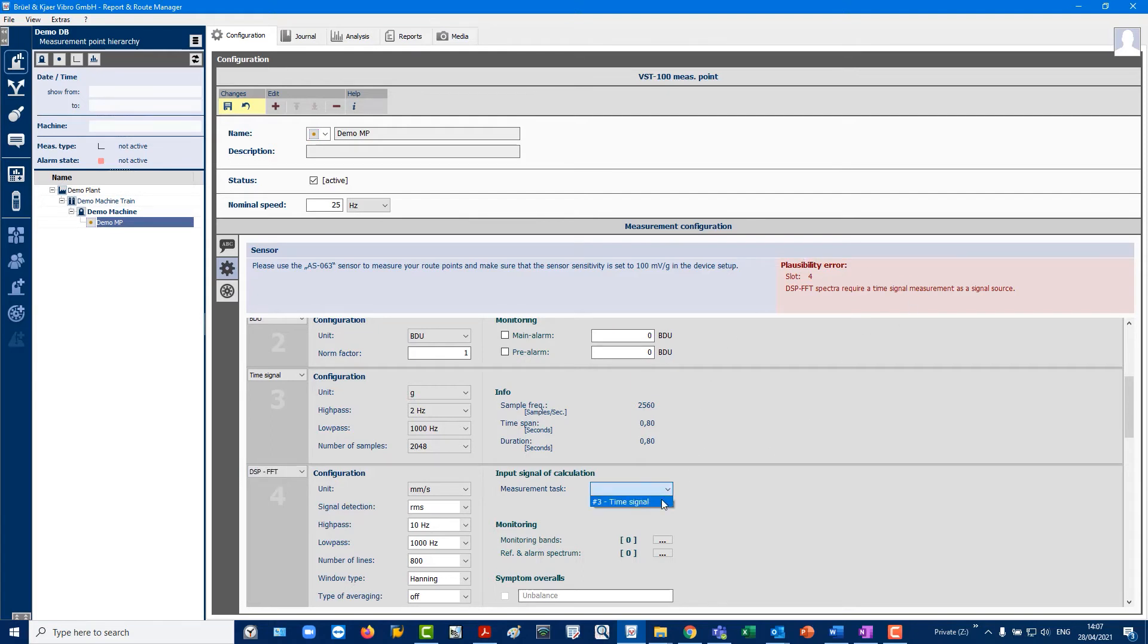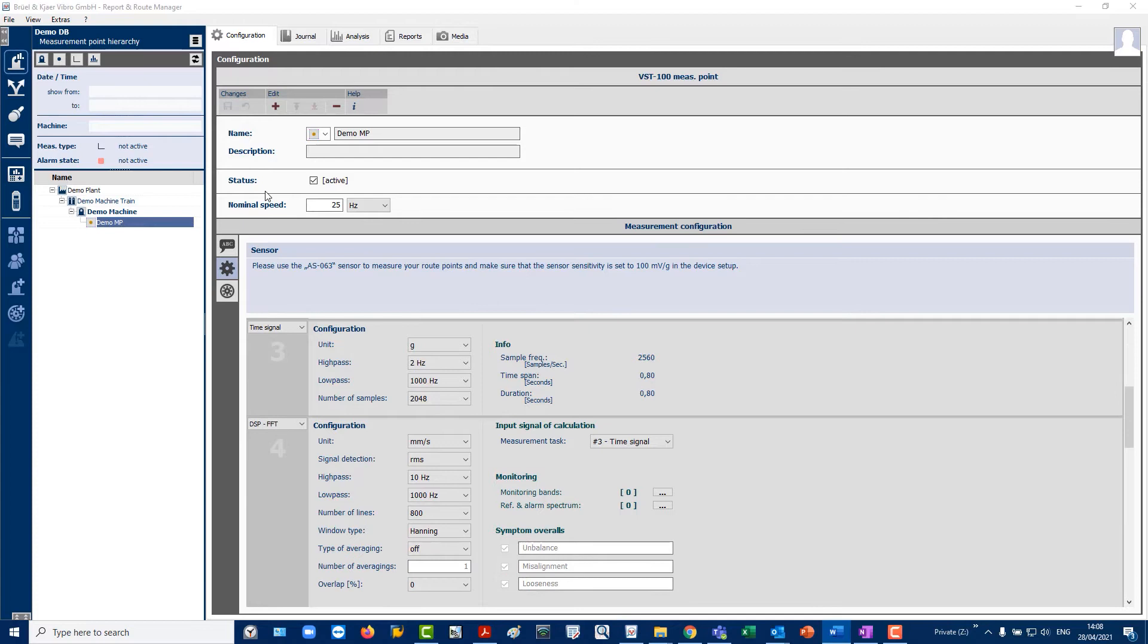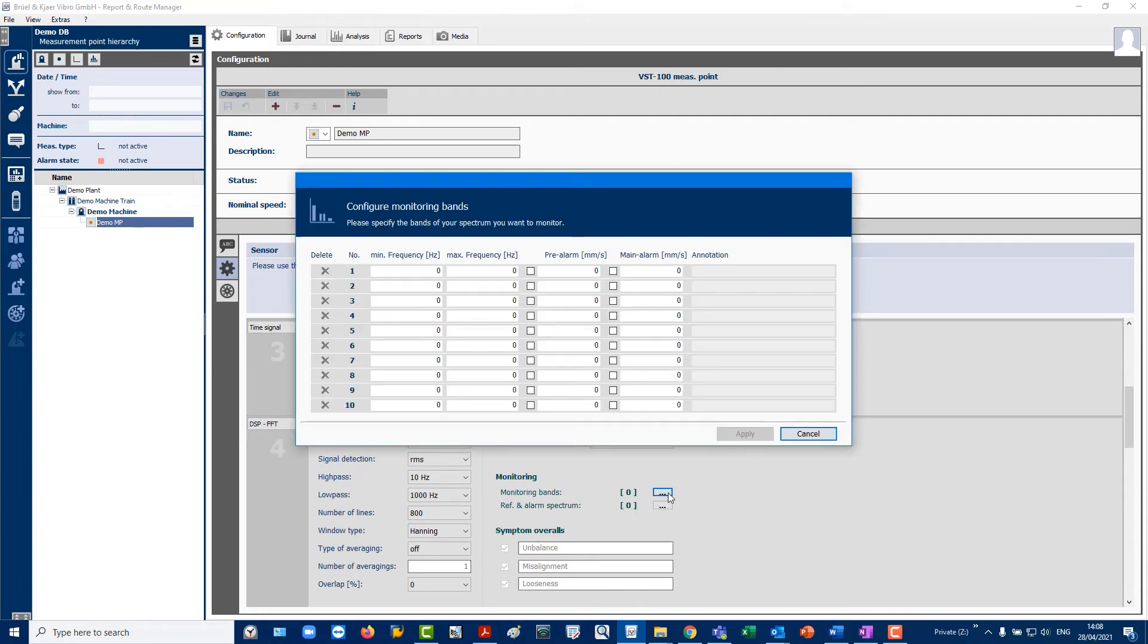Also perform an ISO FFT. You should be able to automatically trend typical symptom overalls that may indicate unbalance, misalignment, or looseness. There is also the possibility to enter alarms for up to 10 monitoring bands for the FFT.